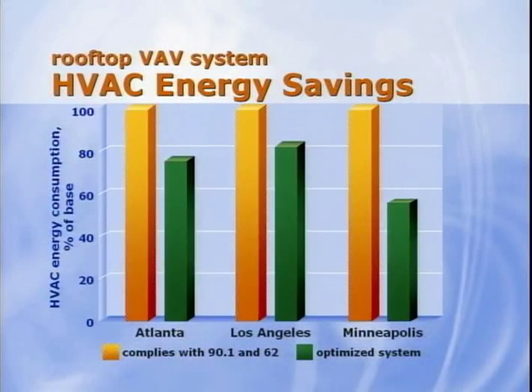We see a lot of rooftop VAV systems that are similar to this typical base system, but in some ways, this base system doesn't even meet the minimum requirements of ASHRAE standards 90.1 and 62. For example, in DDC VAV systems, fan pressure optimization is required by 90.1. So here are the results comparing the same optimized system to a base system that does comply with these standards. The optimized rooftop VAV system reduced HVAC energy by 24% compared to the 90.1 and 62 compliant system in Atlanta, 19% in Los Angeles, and still by about 45% in Minneapolis.